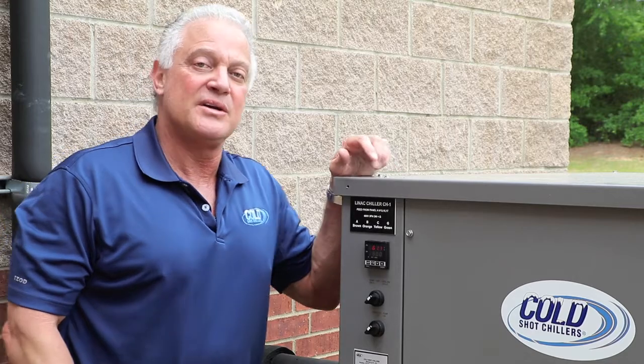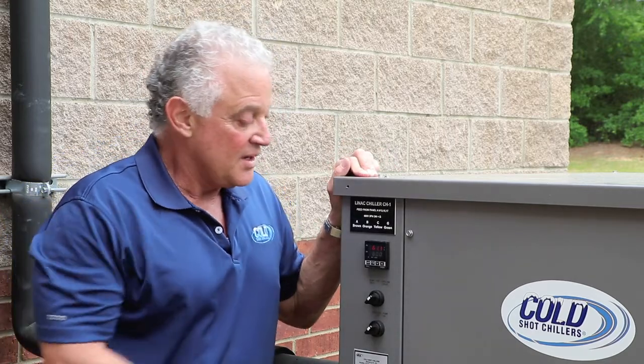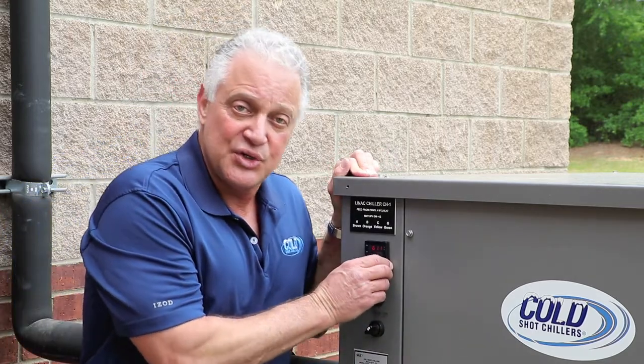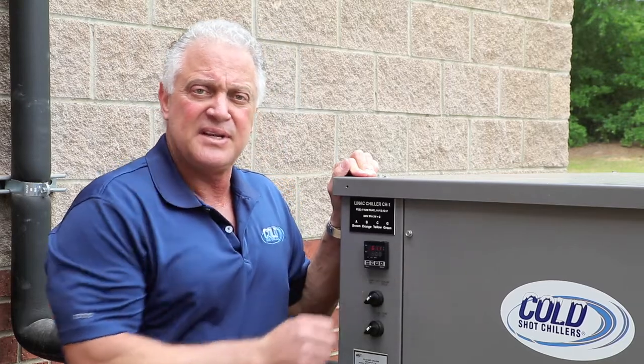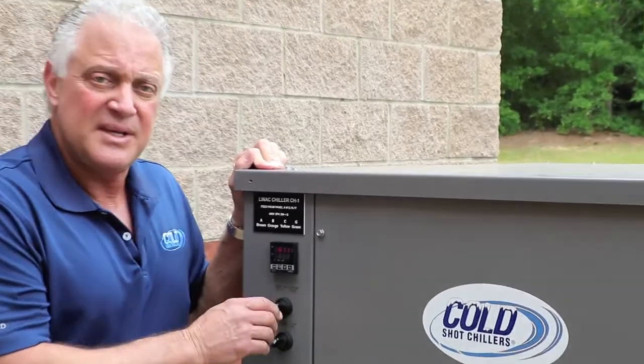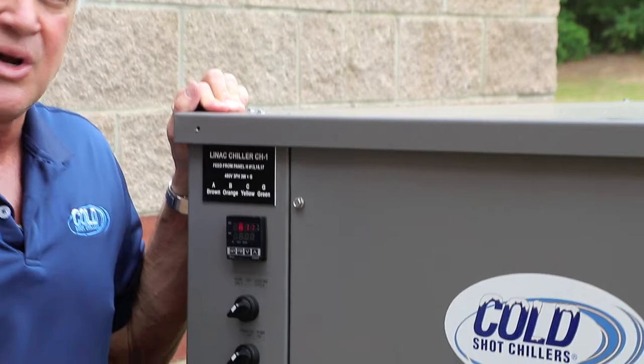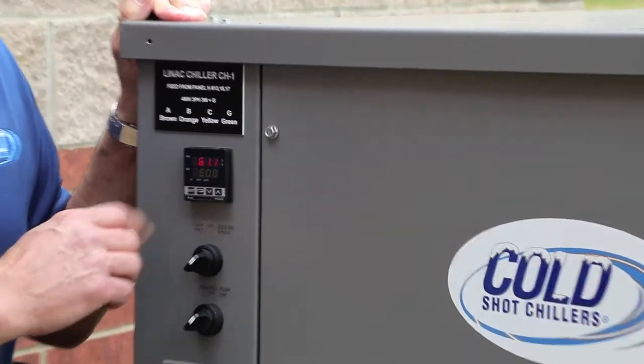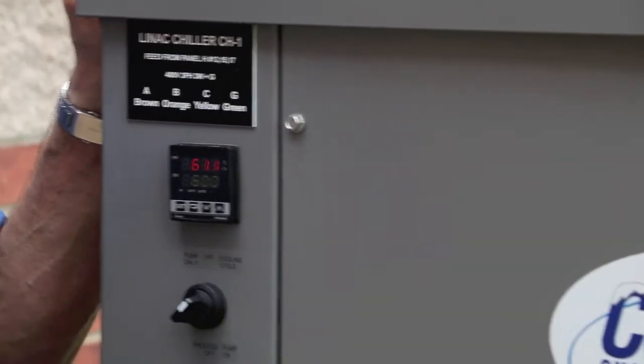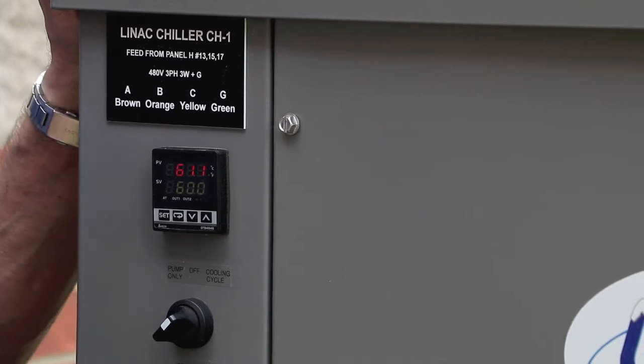Okay, now let's come over here and look at the temperature controller on the machine. When we look at this temperature controller, we're going to see two values. We're going to see an SV and a PV. The PV is the process water temperature within the cooling loop, while SV is the actual set value that the chiller is going to try and maintain.